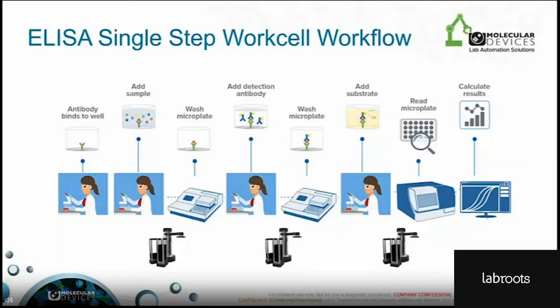The single-step system moves the plate from the hotel to the washer, then back to the hotel so the scientist or technician can perform antibody additions. After storing the labware back in the plate hotel, the S-Lab robot moves the plate to the microplate washer for its second wash. The scientist or technician must manually add the substrate before placing it back in the hotel so the robot can shuttle the plates to the microplate reader for data collection. This work cell does not offer much room for the addition of other instruments over time, primarily due to the reach of the robotic arm.